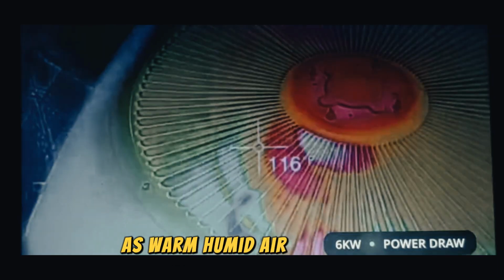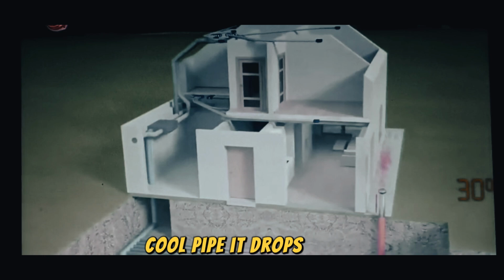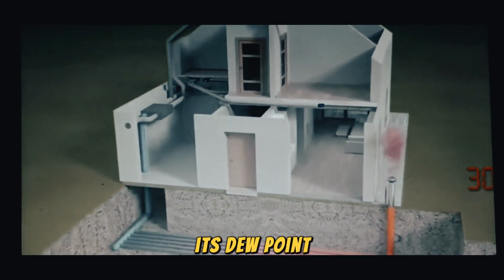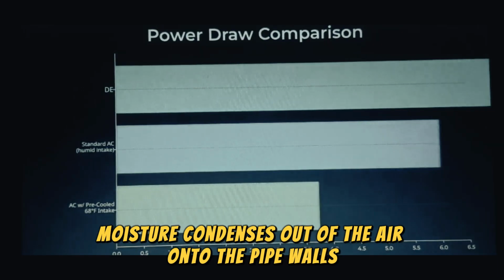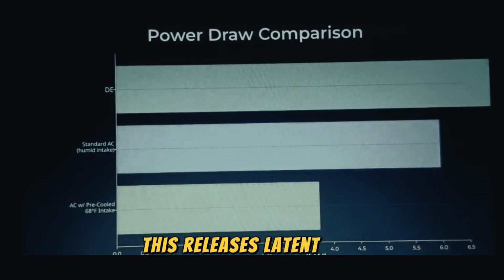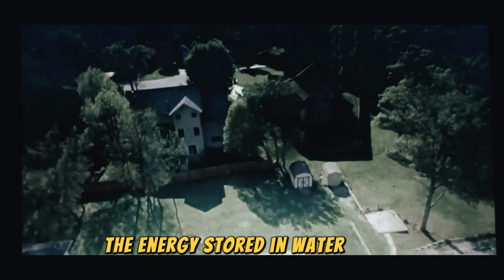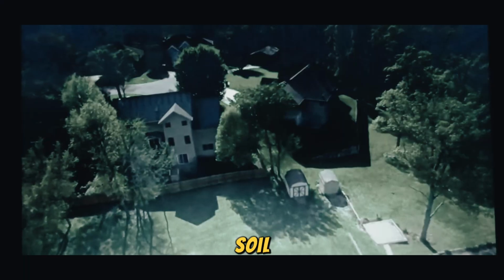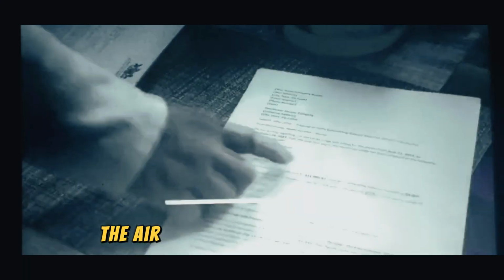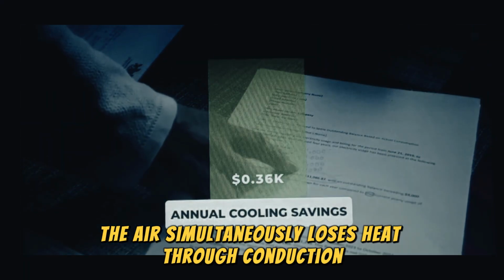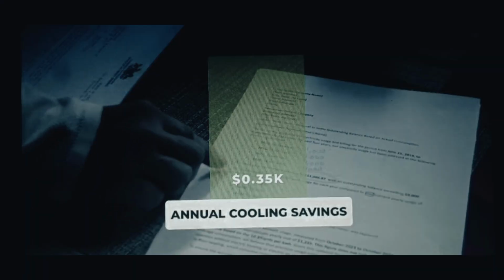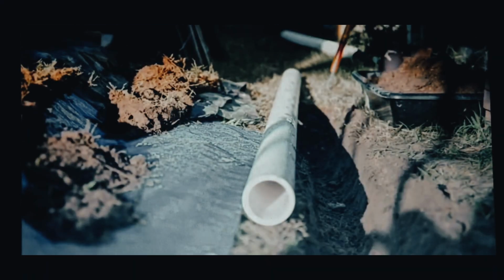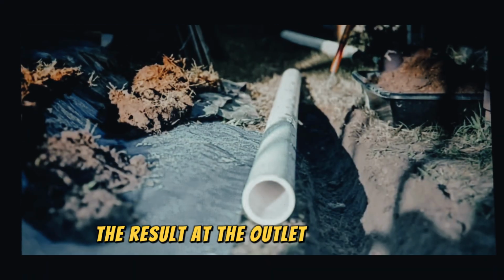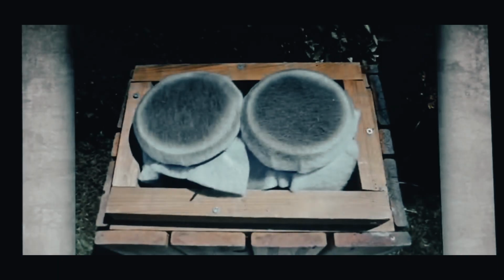As warm humid air enters the cool pipe, it drops below its dew point. Moisture condenses out of the air onto the pipe walls. This releases latent heat, the energy stored in water vapor, into the soil. The air simultaneously loses heat through conduction, and it loses moisture through condensation. The result at the outlet is air that is not just cooler, but drier.